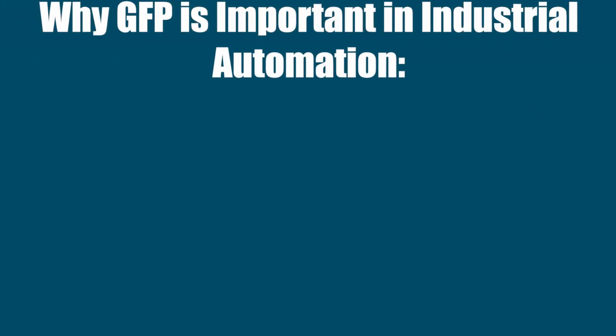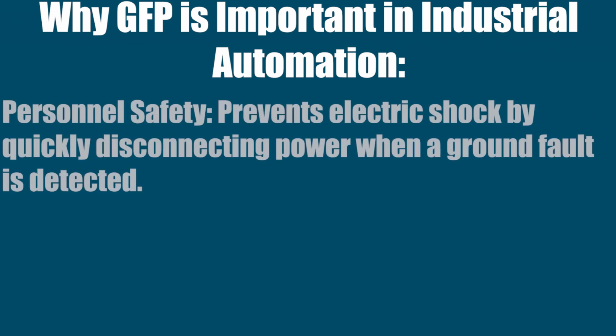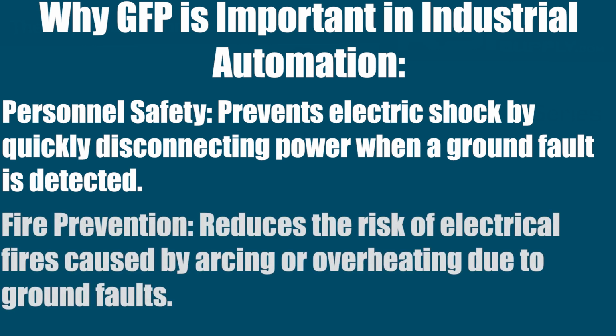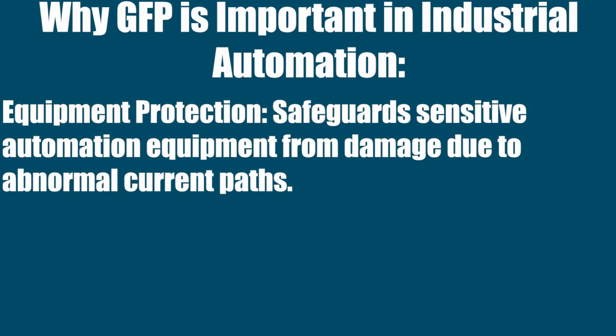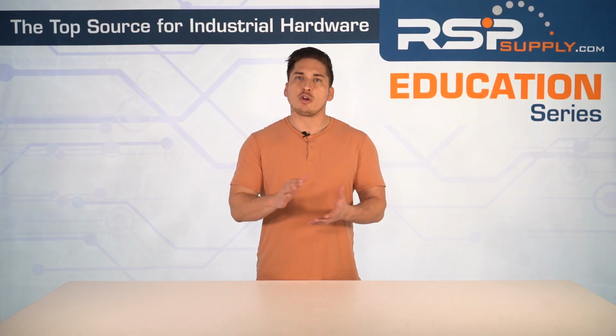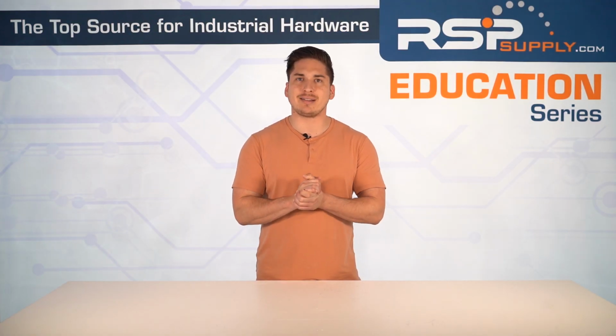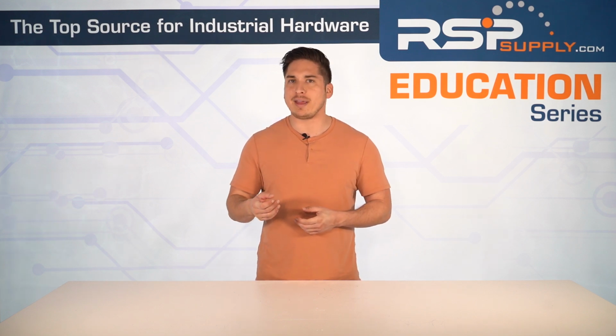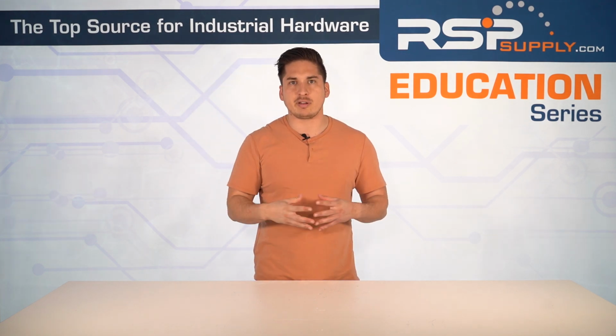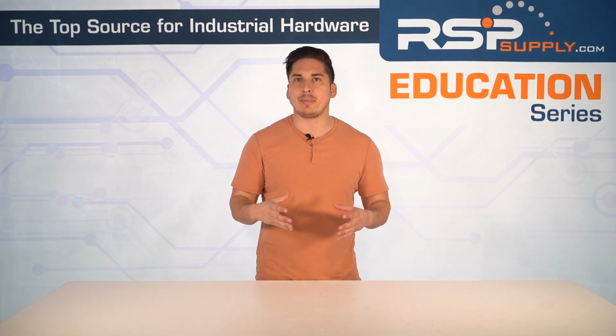So why is ground fault protection so important in industrial automation? First off, personnel safety, quite obvious. It prevents electrical shock by quickly disconnecting the power when a ground fault is detected. Fire prevention is another factor. GFP reduces the risk of electrical fires caused by arcing or overheating due to ground faults. Equipment protection, right? GFP safeguards sensitive automation equipment from damage due to abnormal current paths. In summary, ground fault protection is a proactive safety mechanism that detects and interrupts ground faults before they escalate into serious hazards. This ensures the reliability and safety of an industrial automation system.